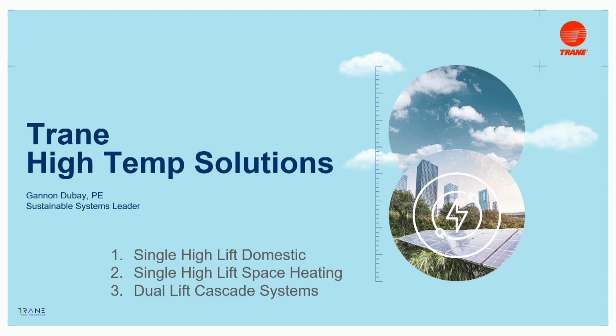So I'm going to touch briefly on single lift machines. As some of these other gentlemen have already kind of explained and will be explaining how some of this stuff works and the benefits of using these. But the reason that high temp hot water is kind of a challenge when you think about geothermal, or even on the air source side when you think about a cold climate, is really the lift requirements, right? Using 0-degree air or 32-degree water and then trying to lift that over 100 degrees and produce 180-degree water is really difficult for your traditional HVAC equipment, okay? And so while we do have some stuff that can meet those needs that I'm going to touch on briefly here, I'm also going to end my short time here by talking about an alternative to that option where we kind of break that lift into. But before we get to that, let's talk about what I like to call our single lift options.